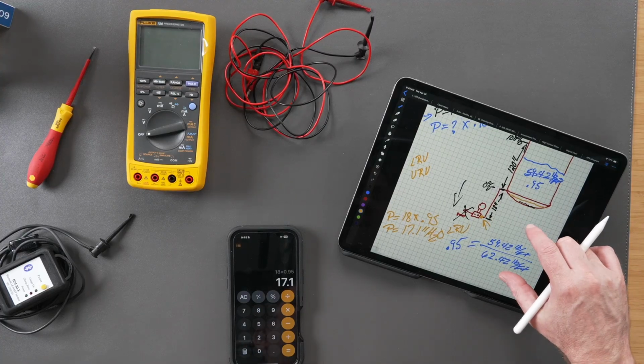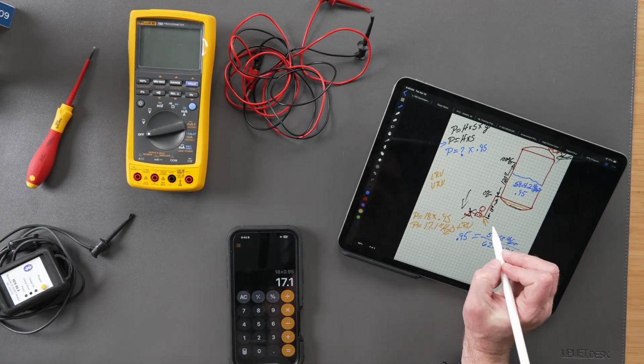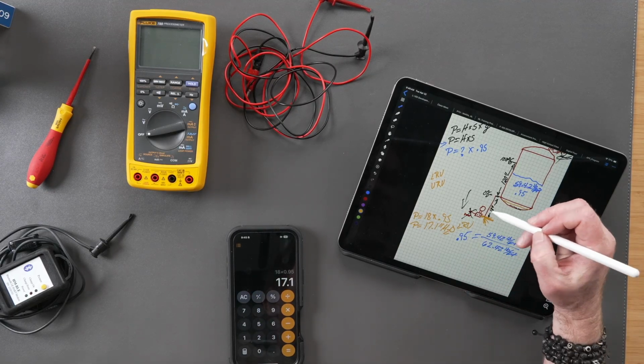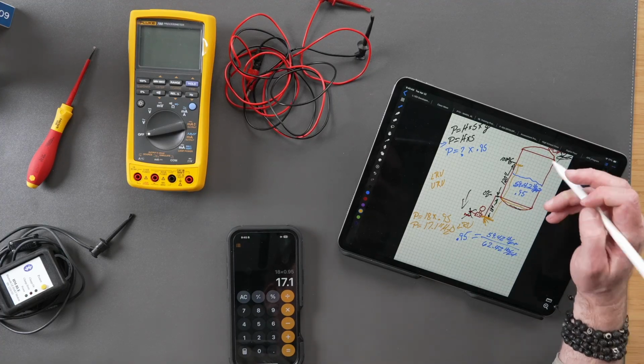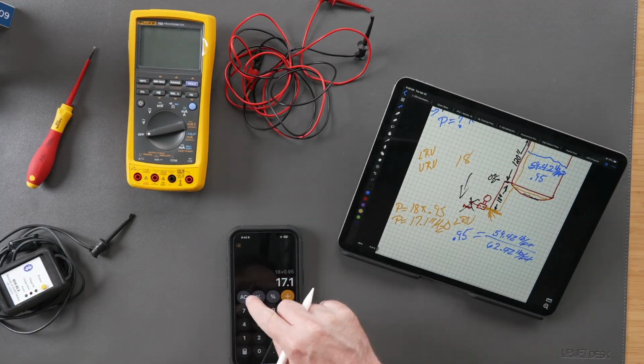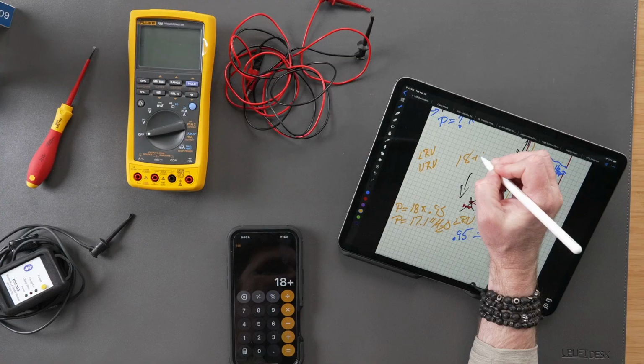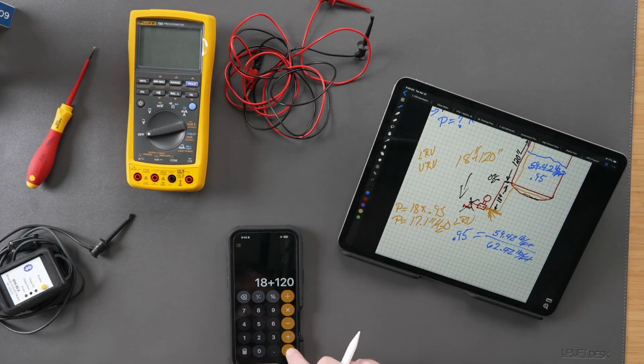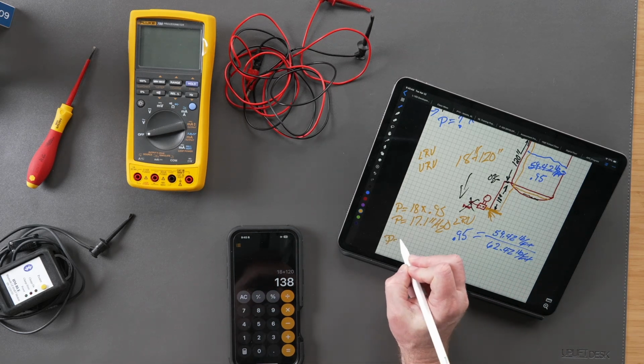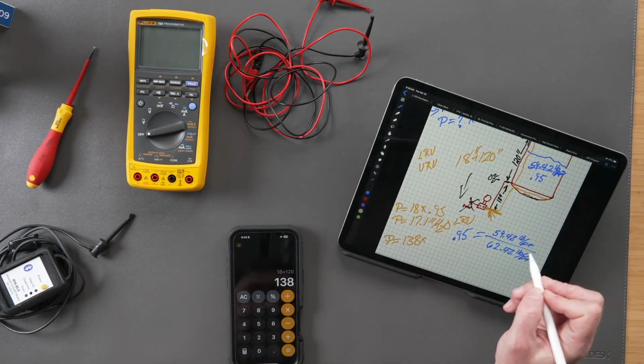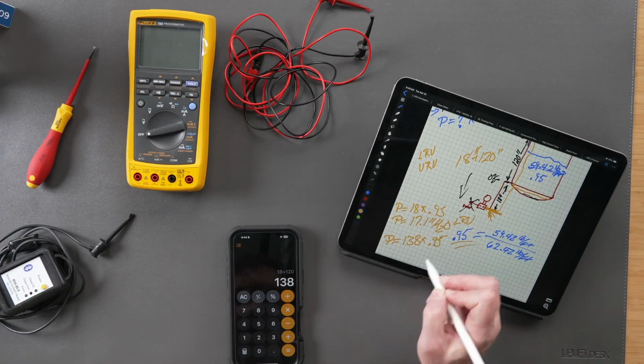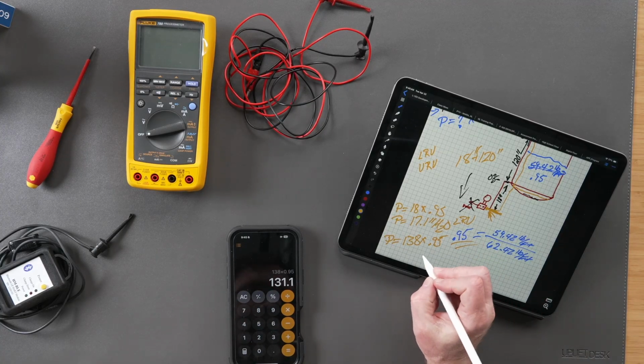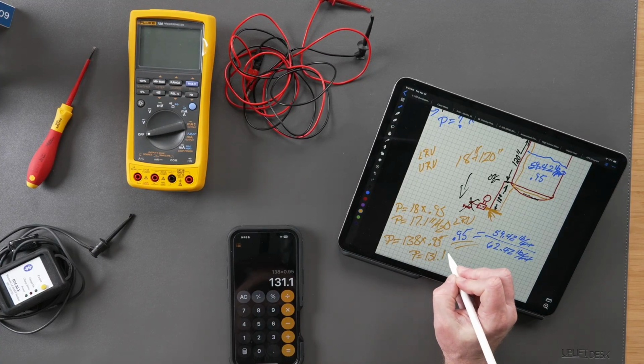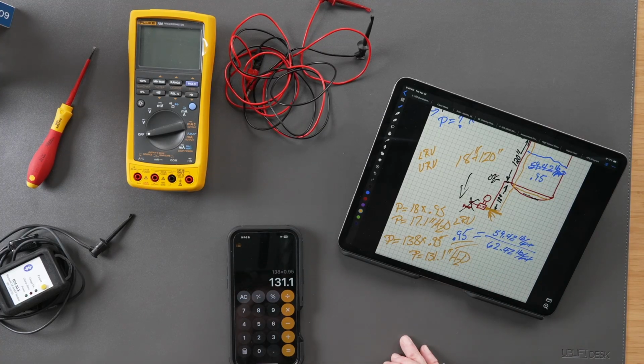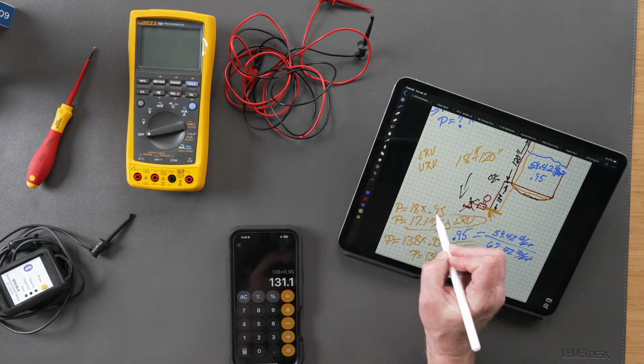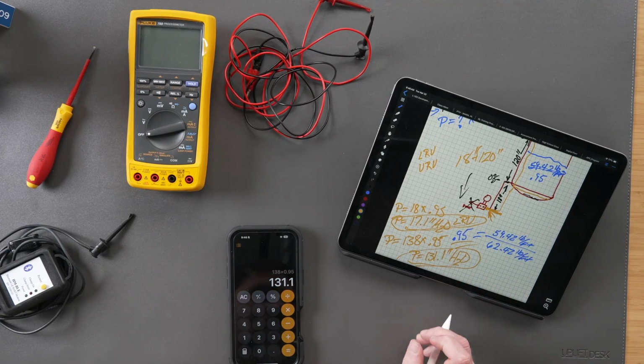Let's go up and do our URV. This is everything above this point - same place we're feeling pressure, but now it's filled all the way up to right here. So I have 18 inches plus 120 inches, which gives me a height of 138 inches. Pressure is equal to a height of 138 inches multiplied by a specific gravity of 0.95, which gives me 131.1 inches of H2O. We've converted that into pressure now. So my LRV is 17.1 and my URV is 131.1 - you might want to remember that.